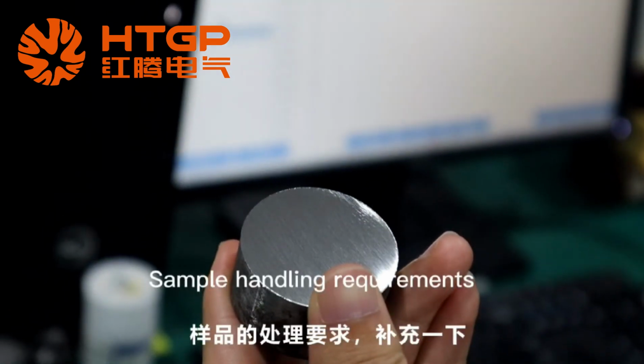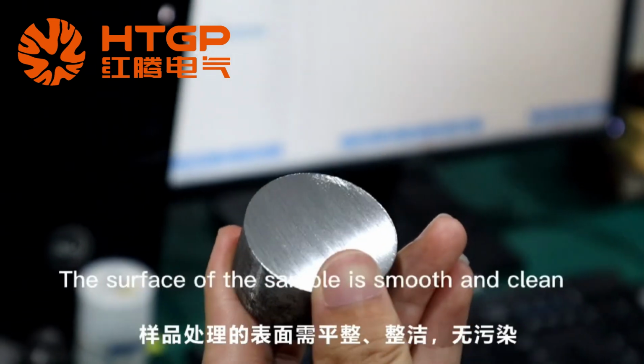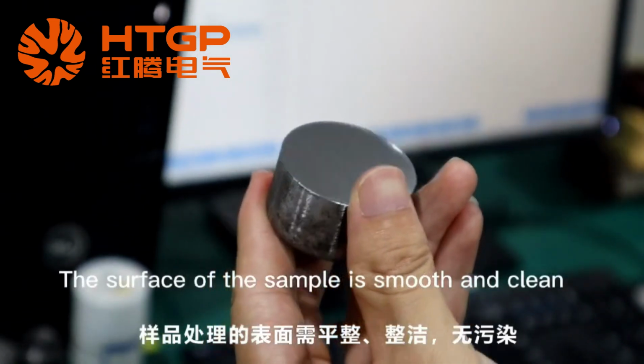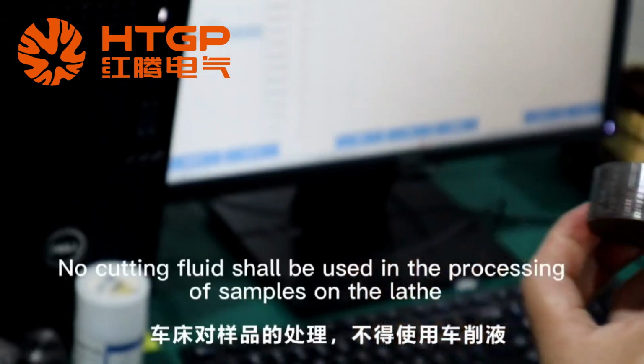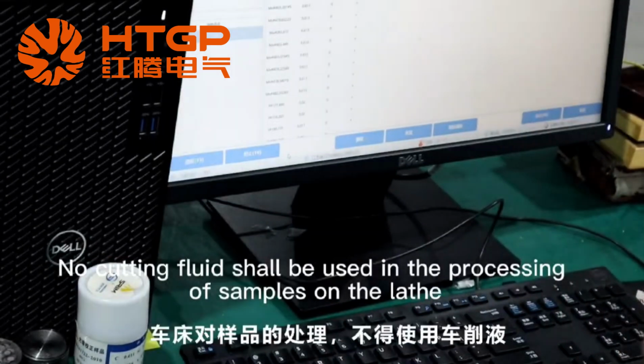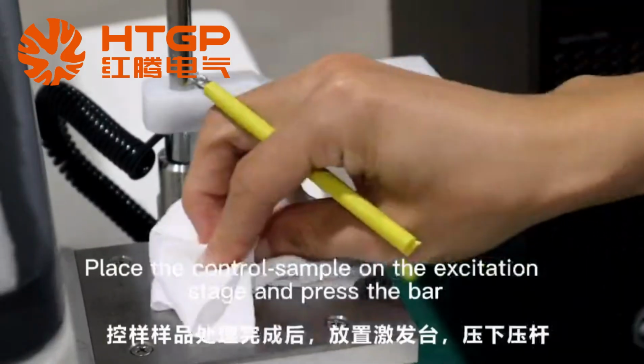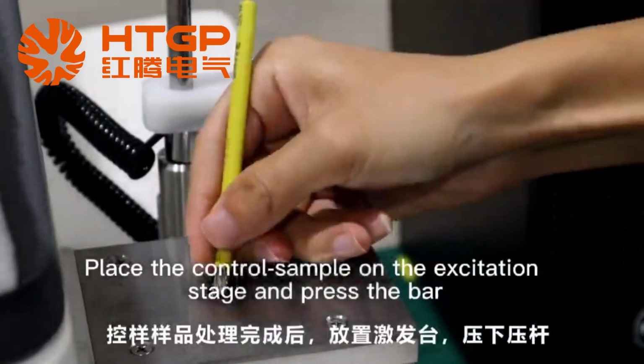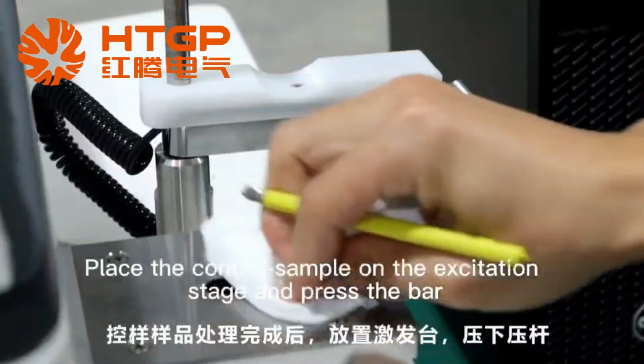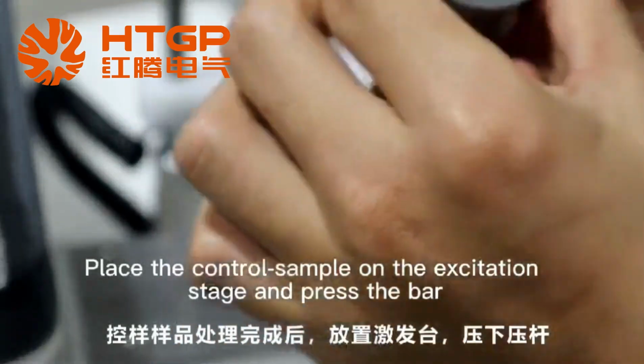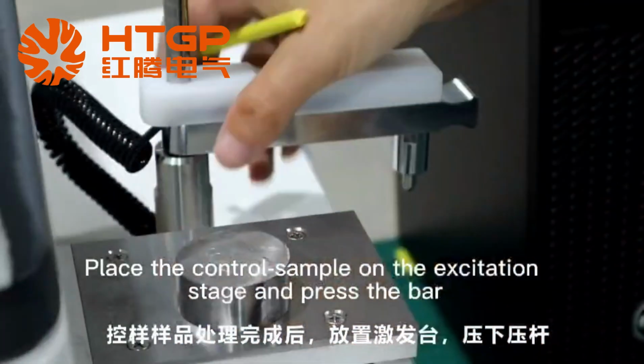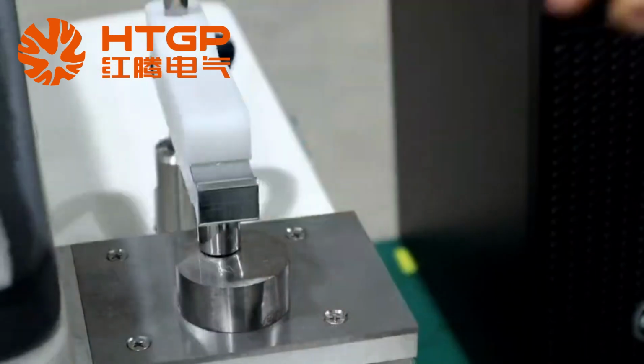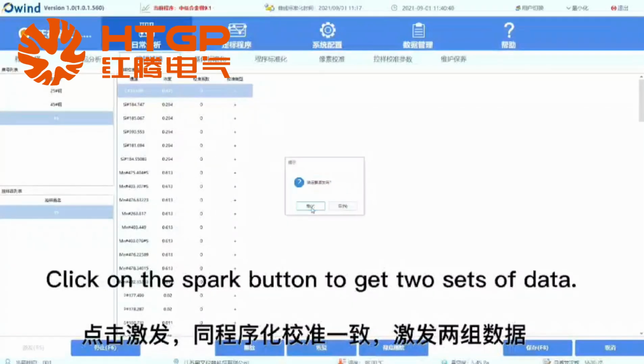Sample handling requirements. The surface of the sample is smooth and clean. No cutting fluid shall be used in the processing of samples on the lathe. Place the control sample on the excitation stage and press the bar. Click on the Spark button to get two sets of data.